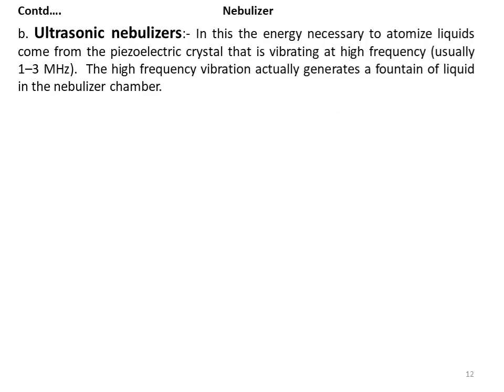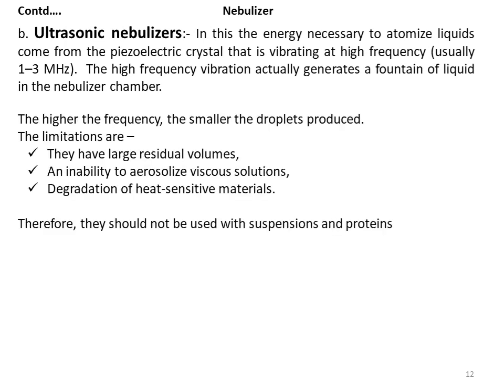Next is ultrasonic nebulizers. The energy necessary to atomize liquids comes from a piezoelectric crystal vibrating at a high frequency of about 1 to 3 MHz. The high-frequency vibration generates a fountain of liquid in the nebulizer chamber — the higher the frequency, the smaller the droplets produced. However, ultrasonic nebulizers have limitations: they have large residual volumes with large losses of formulation; they are unable to aerosolize viscous solutions; and heat-sensitive materials may degrade due to heat produced by vibration. Thus, they are not suitable for suspensions or protein drugs, as proteins may be denatured by heat.